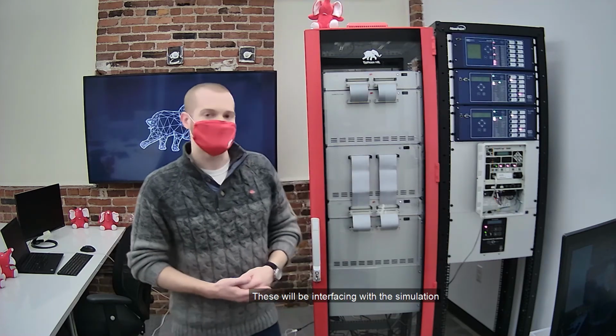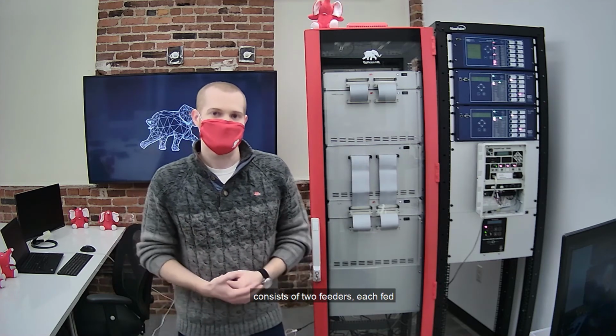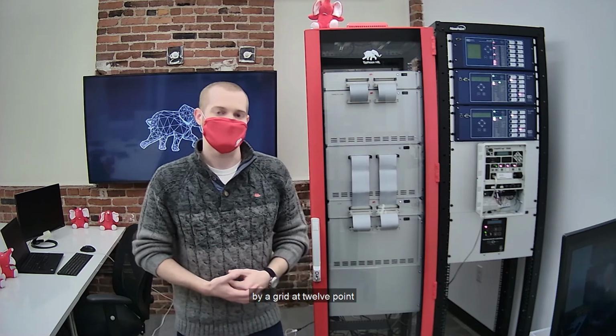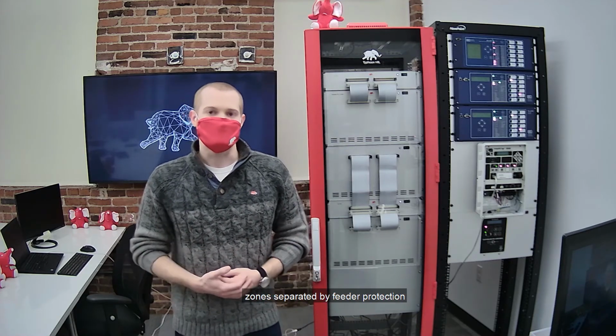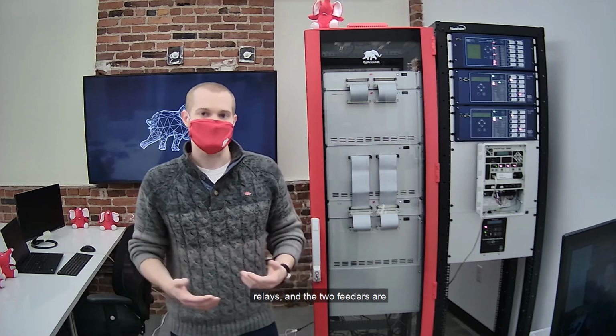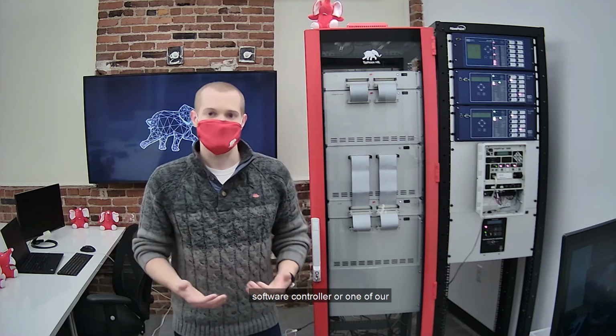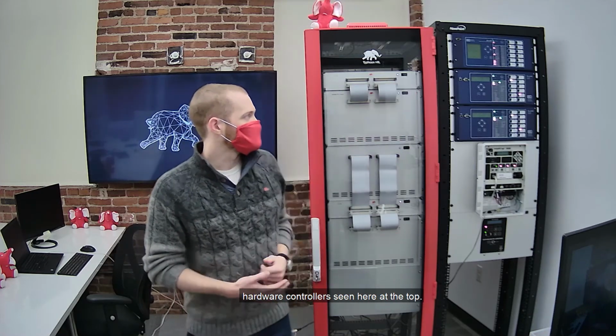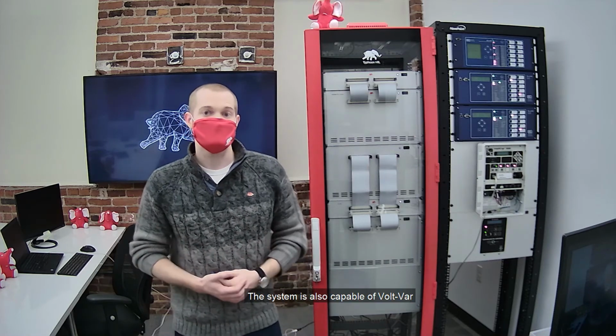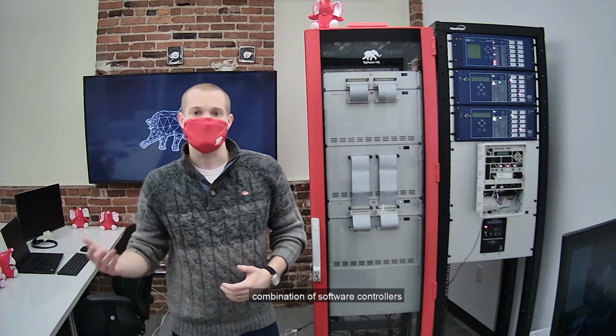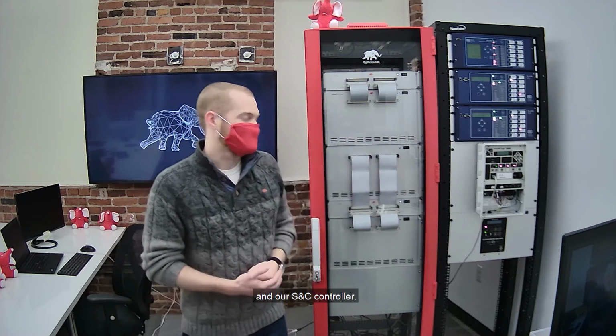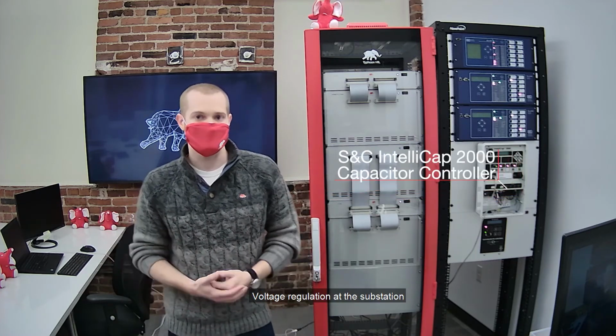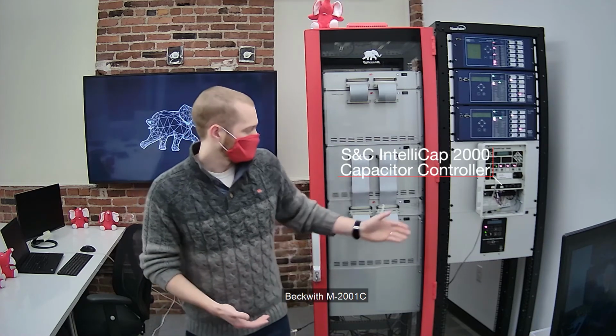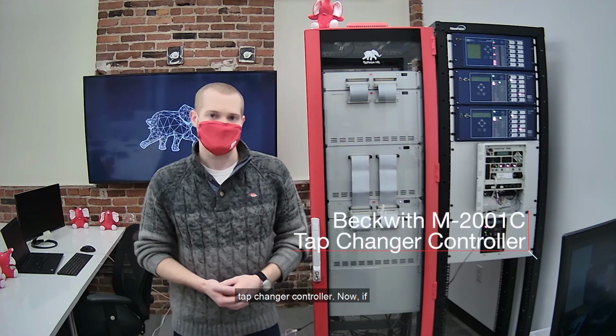These will be interfacing with a simulation of a distribution system, which consists of two feeders, each fed by a grid at 12.47 kilovolts. Each of these feeders is broken into a number of zones separated by feeder protection relays, and the two feeders are connected by an intertie. Each of our relays are controlled by either a software controller or one of our hardware controllers seen here at the top. The system is also capable of volt-var regulation, again through a combination of software controllers and our S&C controller. Voltage regulation at the substation level is handled with the Beckwith M2001C tap changer controller.